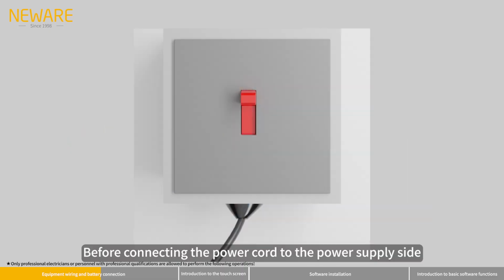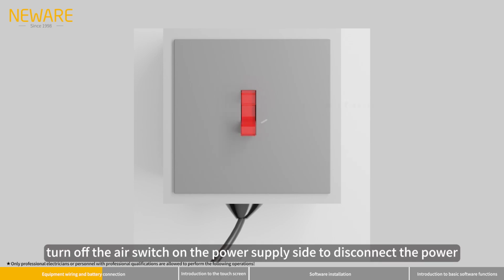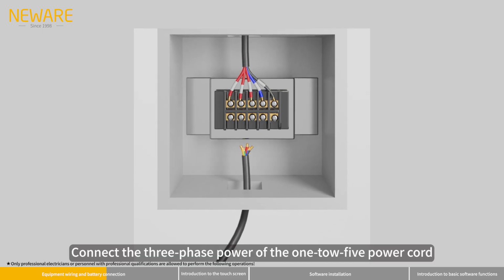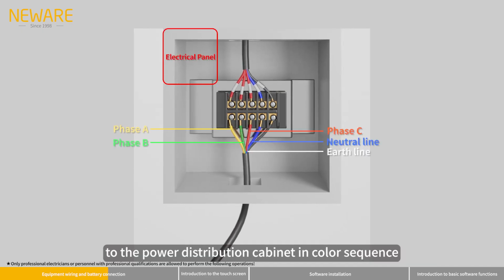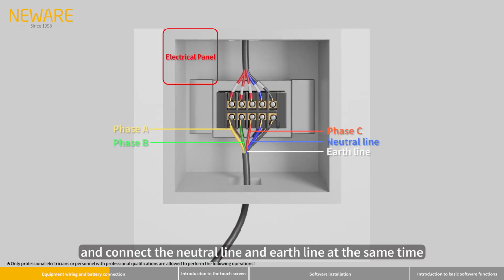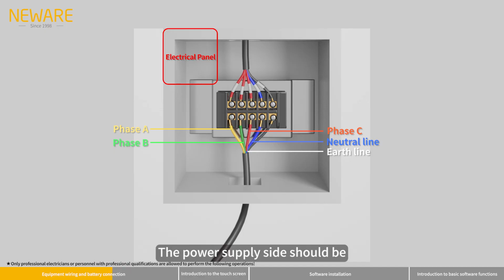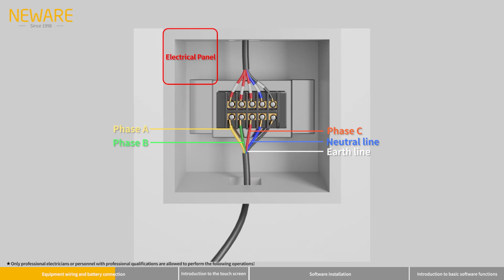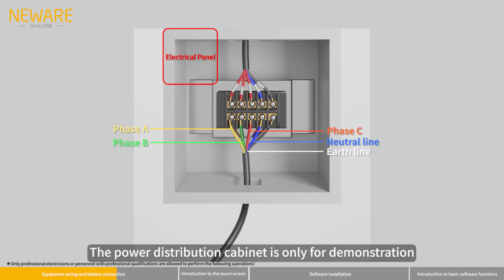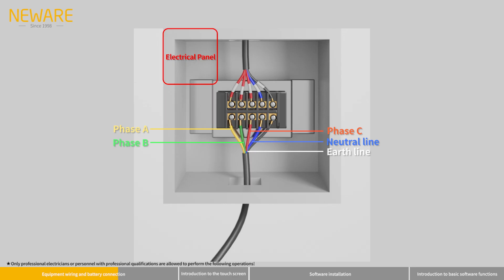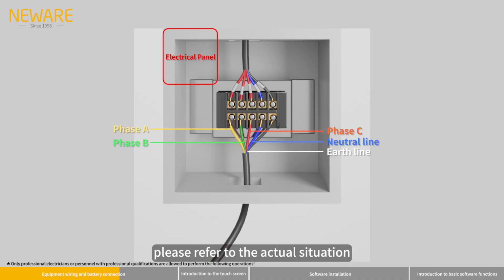Before connecting the power cord to the power supply side, turn off the air switch on the power supply side to disconnect the power. Connect the 3-phase power of the 1 to 5 power cord to the power distribution cabinet in color sequence, and connect the neutral line and earth line at the same time. The power supply side should be 380-volt alternating current. The power distribution cabinet is only for demonstration. Please refer to the actual situation.